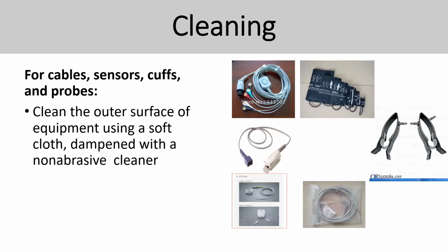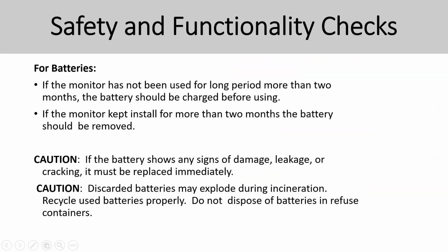So basically you clean the sensor, everything, to make sure it's clean, so the testing will be easier. And safety tests and functional check. Most of the patient monitors come with a battery, so you need to check the battery, whether it's working properly or not. Try to discharge and charge the particular battery to check whether it's working properly or not.